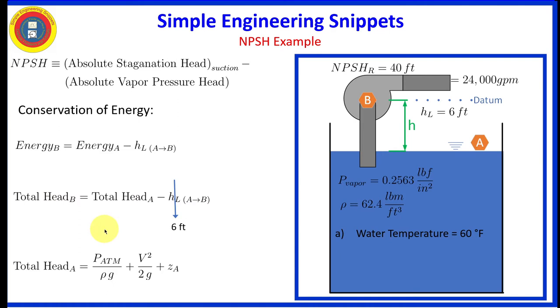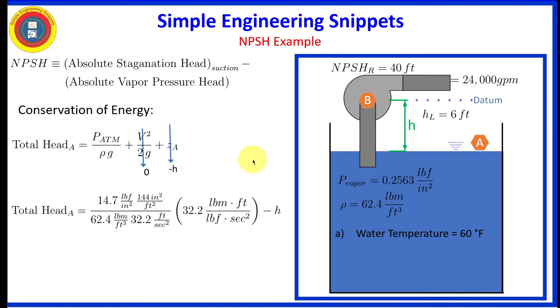We can express this in terms of total head, and keep in mind that the head loss is supplied and is 6 feet. Total head consists of three components: the pressure head, the velocity head, and the elevation head. Since this is a large tank where Alpha is, the velocity head is essentially zero. And again, the elevation of Alpha with respect to our datum is minus H. So going through, we can plug in our numbers. And we get that the total head at Alpha is equal to 33.9 feet minus H. Again, H is what we're looking for. It is the elevation of the pump with respect to the free surface of the water.